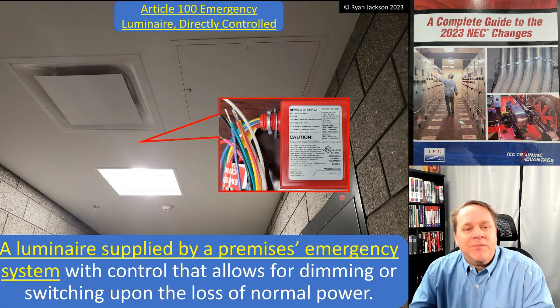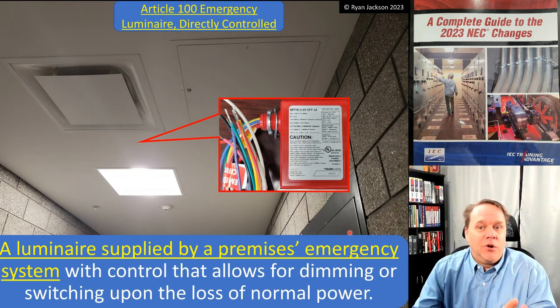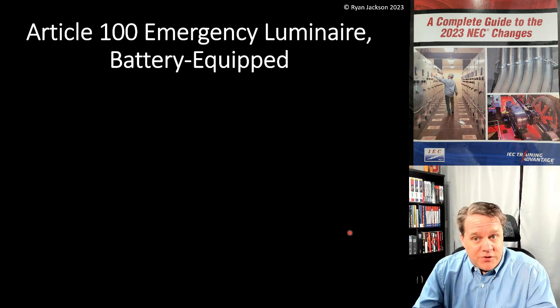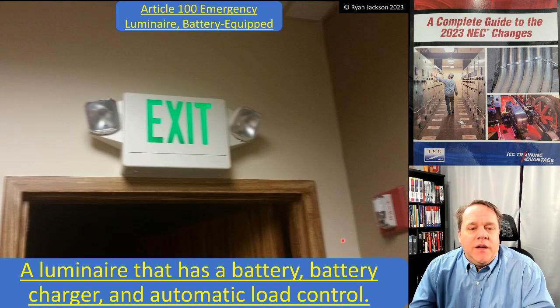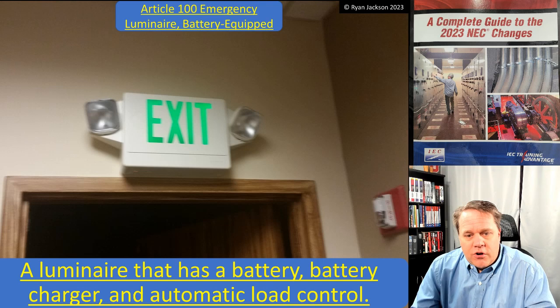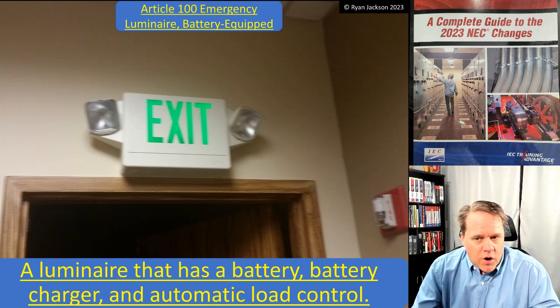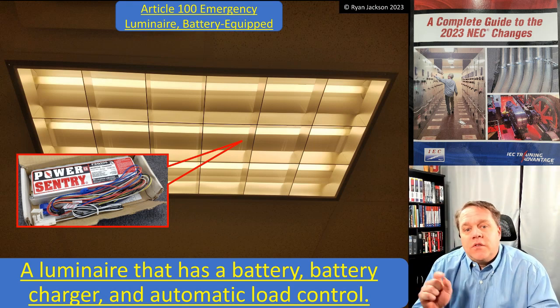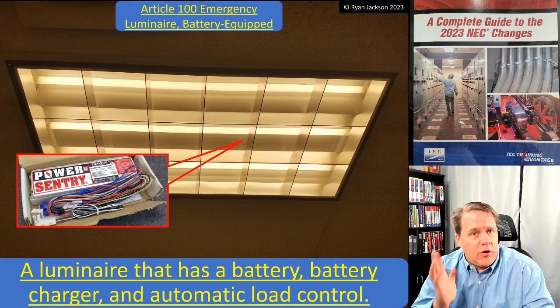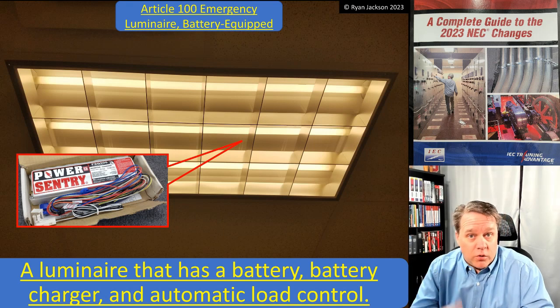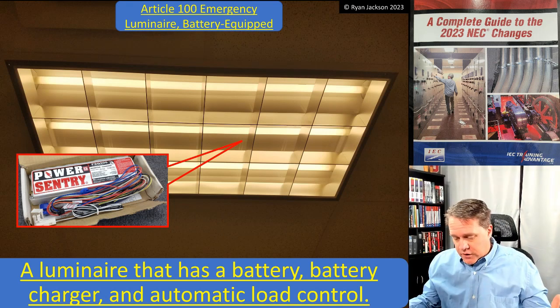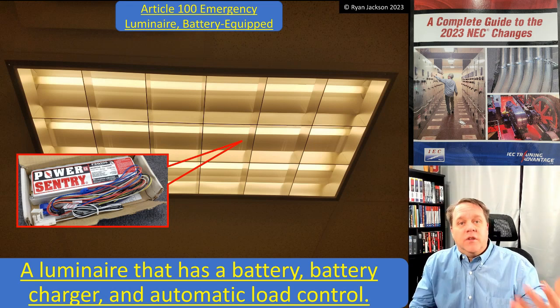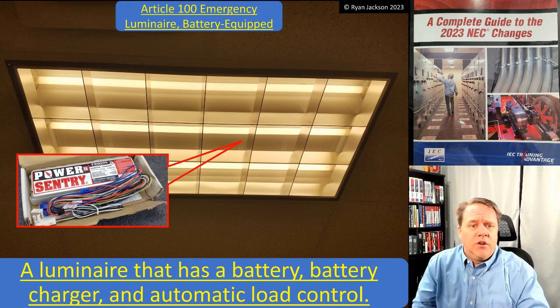It's kind of cool, all the different options we have in lighting control today, especially for emergency illumination — that would be a directly controlled emergency luminaire. We also have a battery equipped emergency luminaire — a new definition that was added. That would be a luminaire that has a battery, a battery charger, and automatic load control. This could be a wall pack, but more likely it's a light like this where it has a battery like an emergency ballast. It's got your normal illumination, your battery, battery charger, and automatic load control, so when the power turns off the battery kicks on and provides the required illumination for up to 90 minutes.